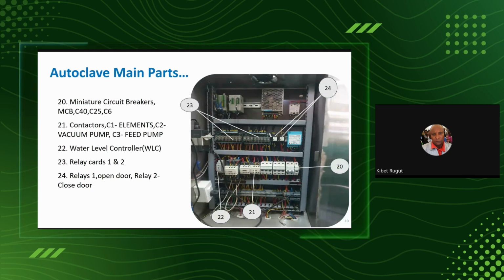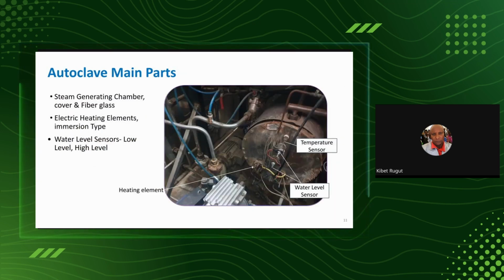The relays, which have so many different functions, are also in a relay card. There are relays there which open the door, which also close the door. So you may look for a knob in some of these autoclaves that you don't find because they are fully electronic type. So when it comes to the big elements, some of the heater elements have been labeled here or have been shown for your easy conception, and piping and also water level sensors. You realize these are very crucial items in the safety of the autoclave, how they look like and where they are located in an autoclave.